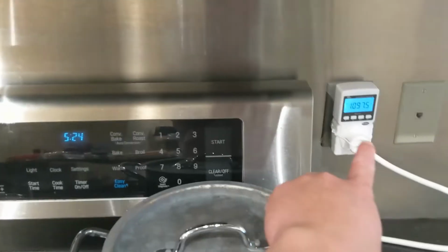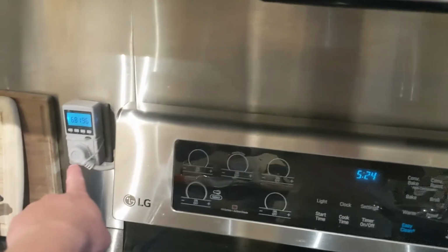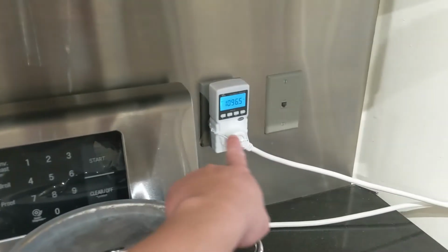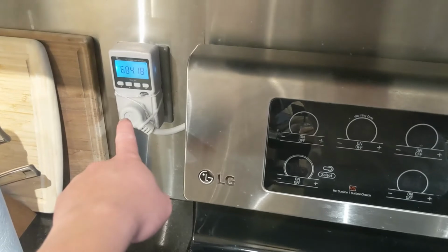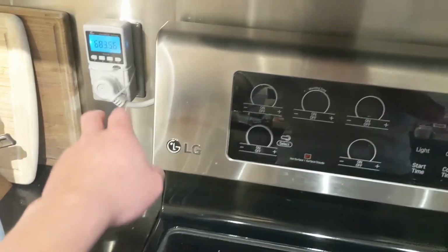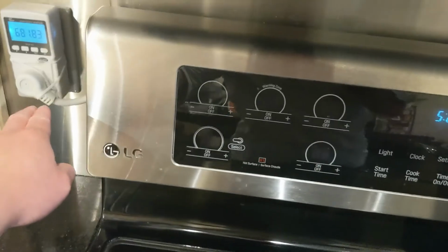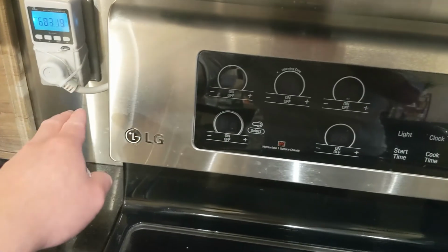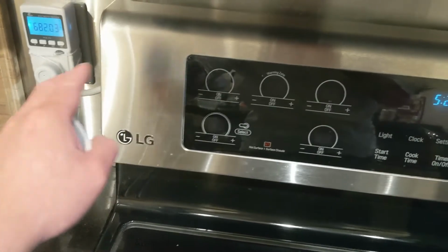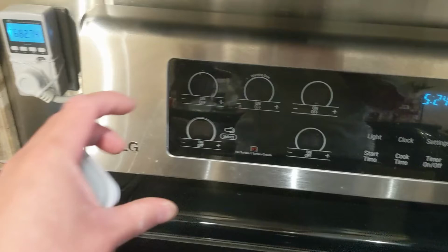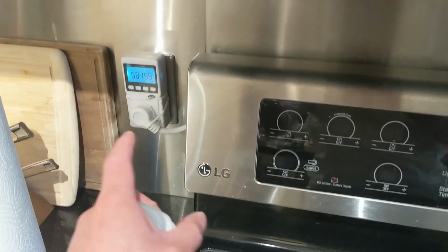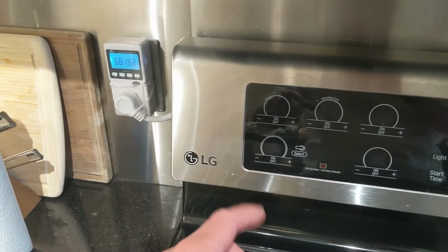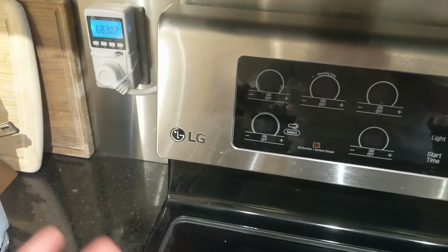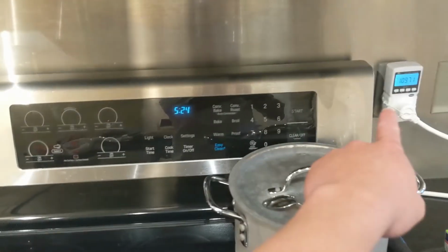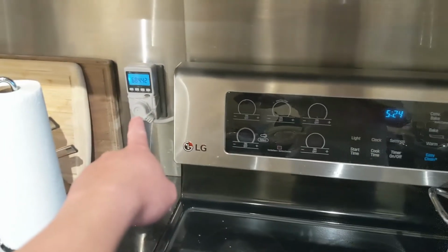So for instance, these two are connected to 11. They're the same one, so it's 1100 and 700, that's 1800, right? But this one I know connects to a 20 amp, which is 2400. And I want to use 80%. Remember the rule of 80? I want to use 80% of 2400, so that's about 2000. I'll leave 400 left. And as you can see, it's always that.